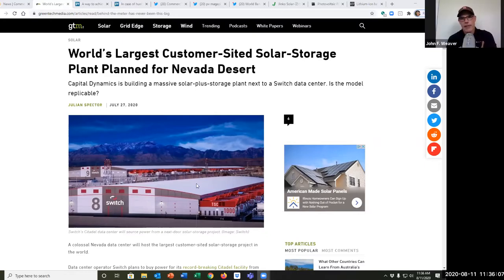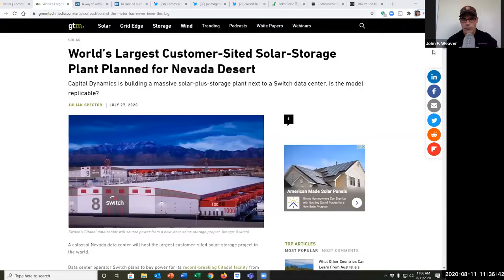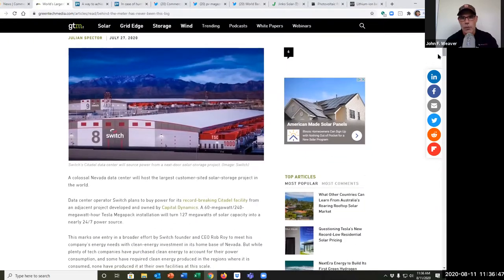Well, the concept of building a power plant at a building - there's a lot of acres that goes into building a solar power plant, but this company has 127 megs of solar, 60 megs of battery inverter. I bet that plant could run 10 hours in the day, 4, 5, 6 hours overnight at 20, 30, 40 megawatts, and run for 24 hours at 50%. They reference almost 24/7 power - 127 megs that could output at 60 megs from 7 a.m. until 5 p.m., and then that storage gets it up to like 16, 17 hours. But if they get down to say a 30 megawatt demand in that structure, that system could run - that's getting close to a 24-hour power plant at this data center.